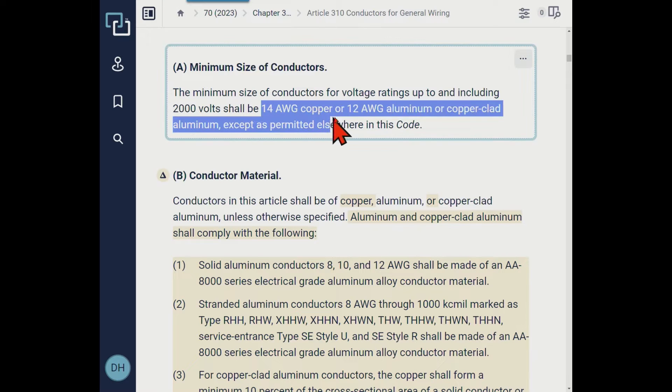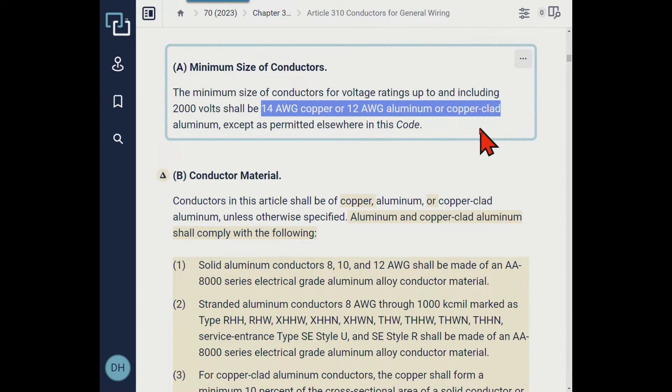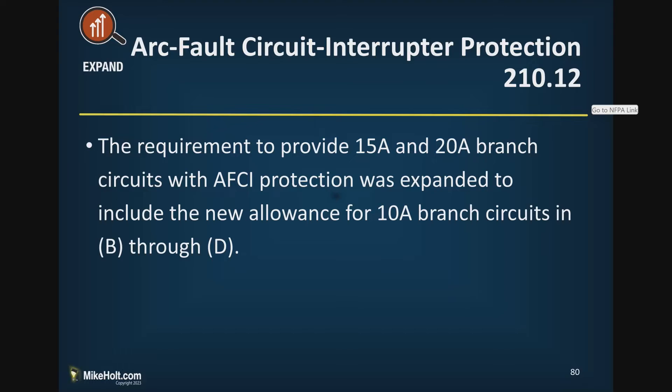Section 310.3 says 14 gauge copper and 12 gauge aluminum or copper clad aluminum. So the code does not allow 14 gauge copper clad, and it doesn't give the ampacity of 14 gauge copper clad. They added all these rules for 10 amp circuits but slipped up — no ampacity was established and no permission for 14 gauge aluminum copper clad. So the 10 amp rule effectively can't be implemented, and we're going to move on.